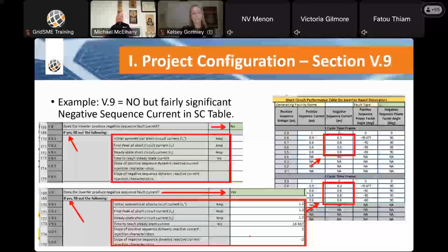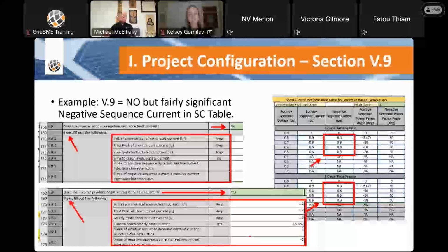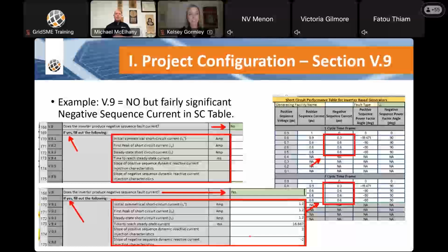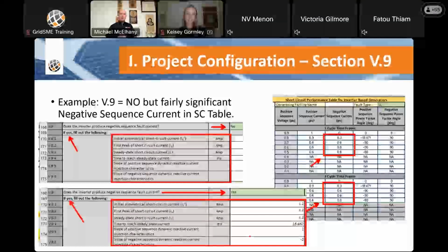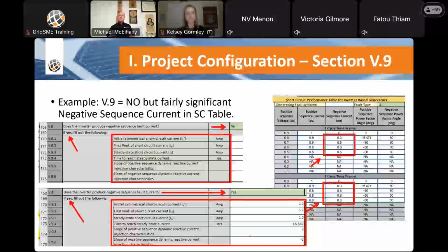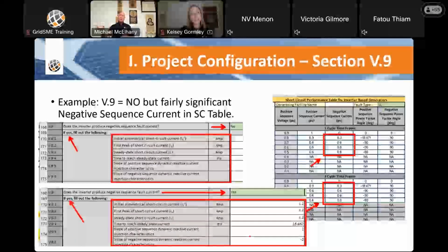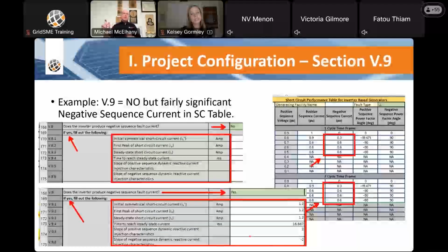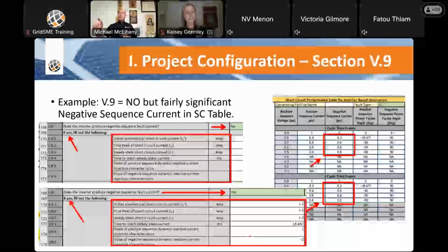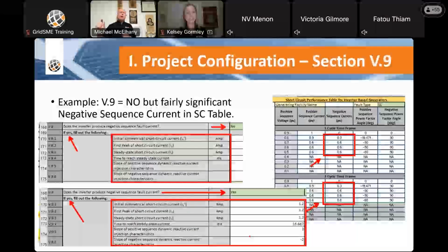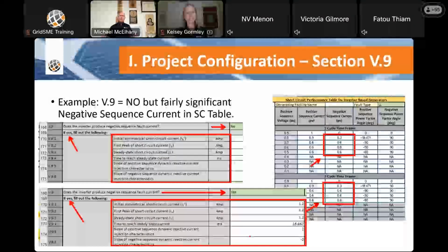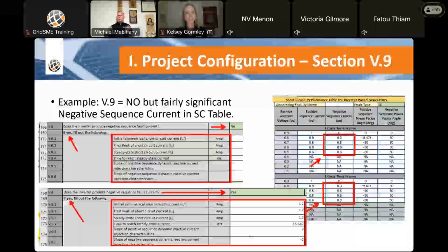The next one is not a bucket or Appendix H specific, but I always like to pull this one out because it can be a gotcha. There's a couple of gotchas that happen here. The top left part of the screen demonstrates the answer was no, but the right-hand one was the short circuit data tables. And for line to line and single line to ground faults, there's 0.3, 0.6 per unit negative sequence current. And so how do we say no?